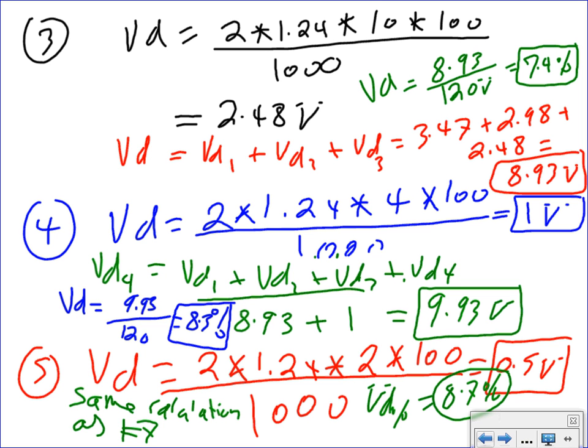A lot of commercial engineers start with 4-aught when we do a parking lot. You go for 4-aught conductor and the voltage 480 or 277, and you push your voltage further distances. Look how many hundred feet. What was the longest distance? 100, 300, 400, 500 feet. 500 feet is a long distance. So a lot of people use 4-aught, 2-aught, 1-aught conductors when they power the parking lot, not because of the amount of power, but because of voltage drop.